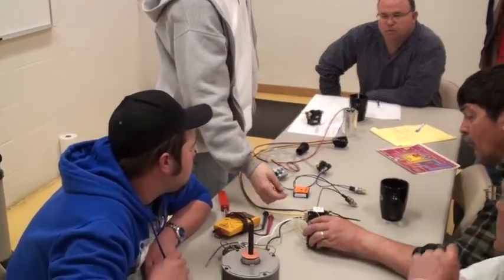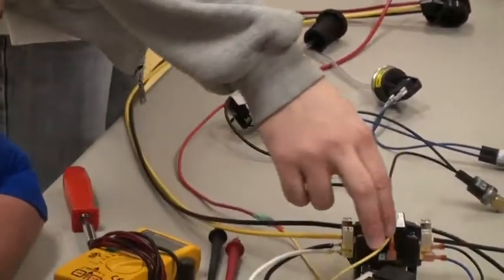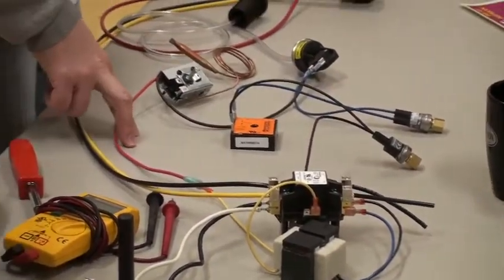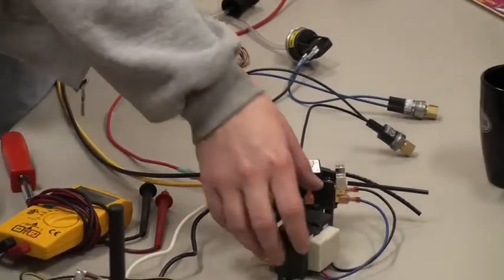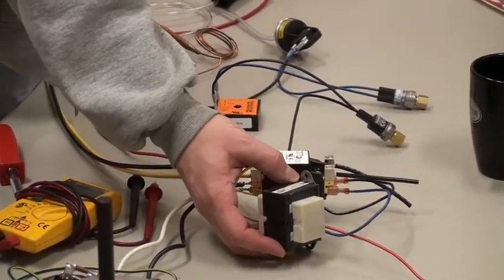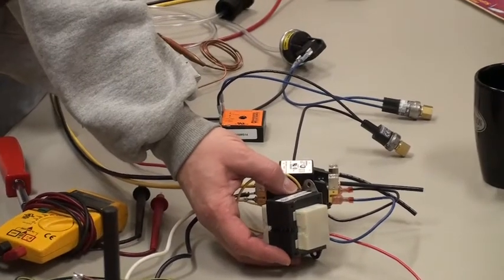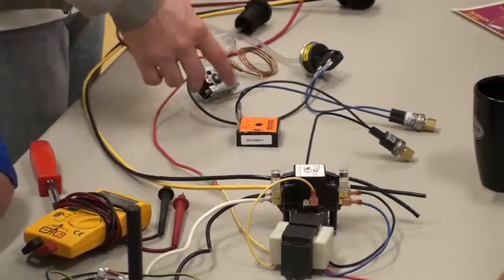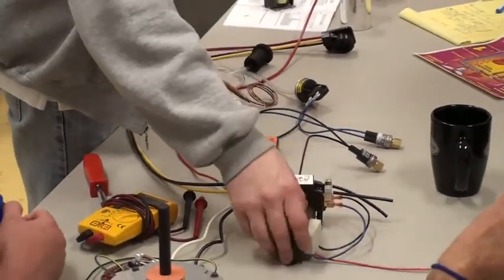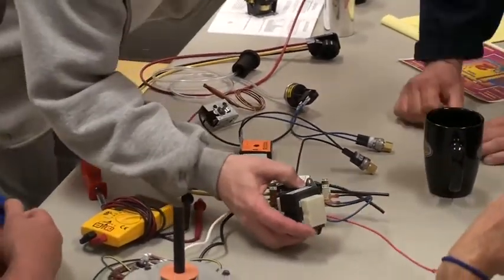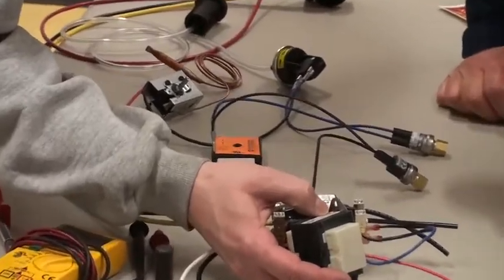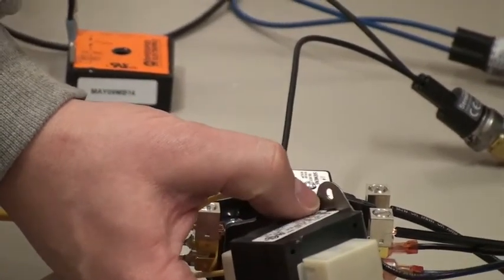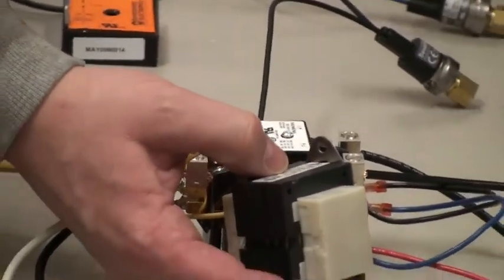You'll know which ones is the 24-volt loop because you'll know which one goes here. The other side goes to the top. If you ever replace a transformer and you're not using one of ours, just read the label. It'll tell you which one's the high-voltage side, which one's the secondary. Just make sure the secondary goes to the 24-volt loop. And make sure you read the side. It'll say common black, and then red's 208, blue is 240. So you're using the common black and the 240-volt blue.